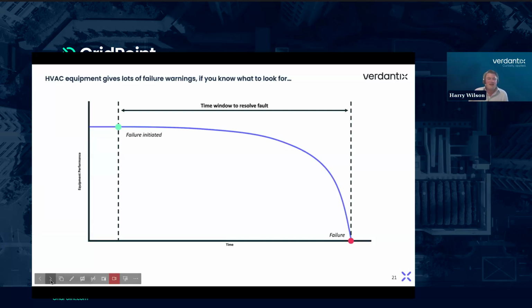On this chart we have equipment performance on the y-axis and time on the x-axis, plotting performance against time with regards to failure. The title is: HVAC equipment gives lots of failure warnings if you know what to look for. The green dot is when failure is initiated. You can see normal operation, a straight horizontal line before that point, and then as you get closer and closer to that ultimate failure event, when equipment performance is zero, it slowly starts to curve down. That's because it degrades over time, and it degrades a lot quicker the closer to failure it is.